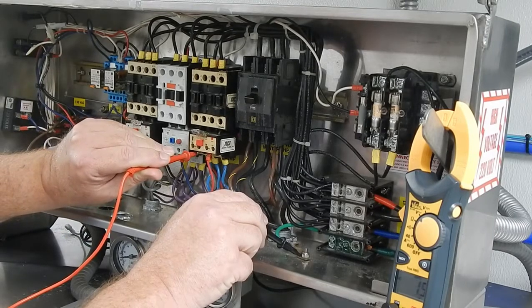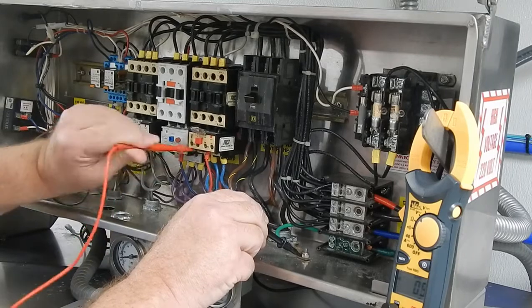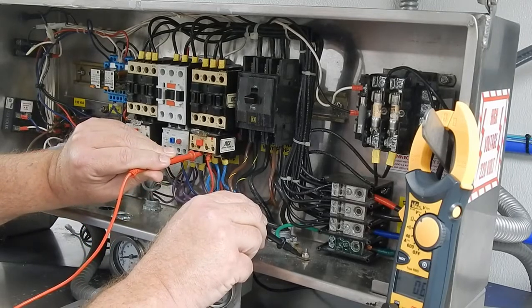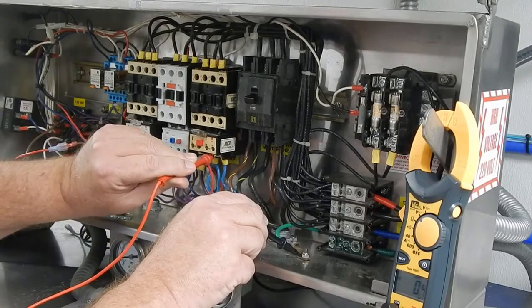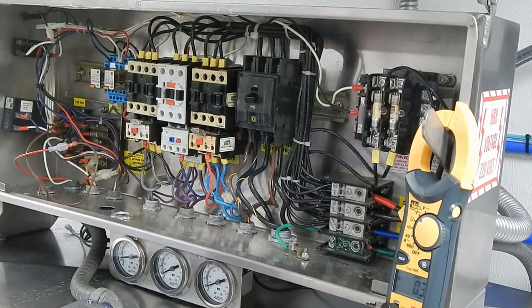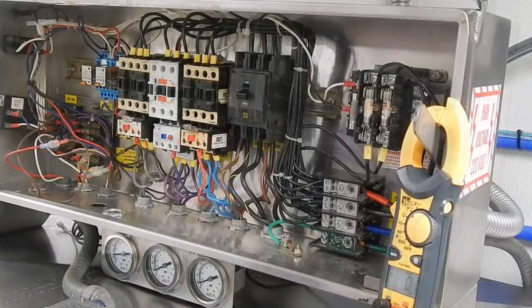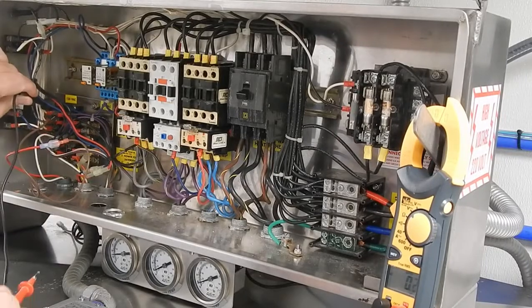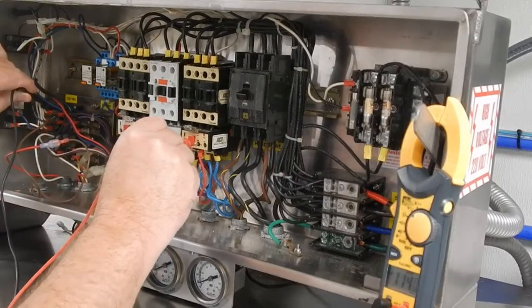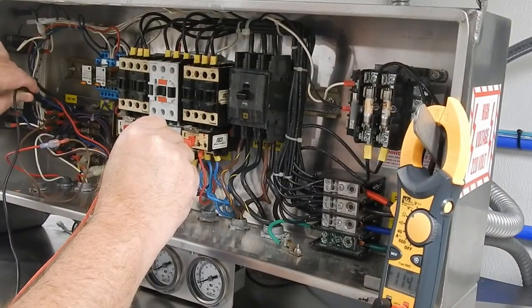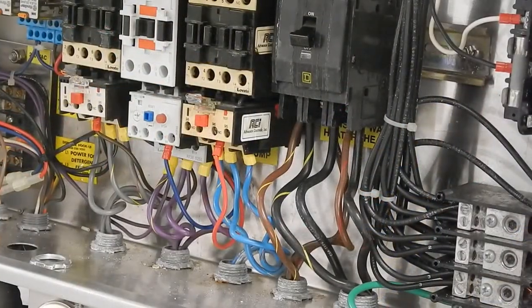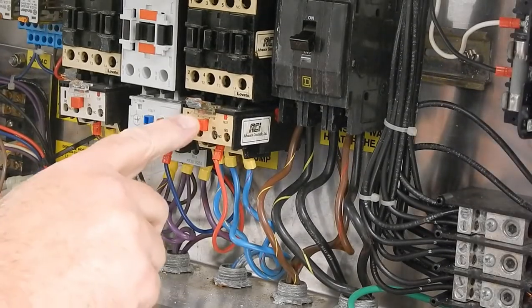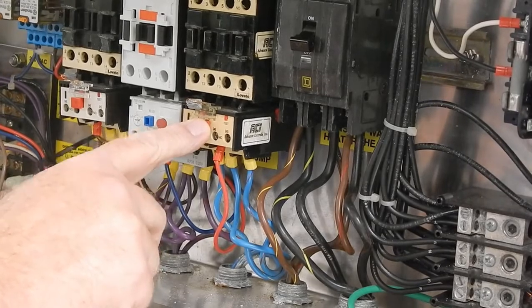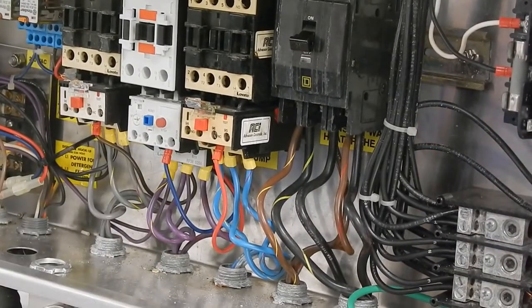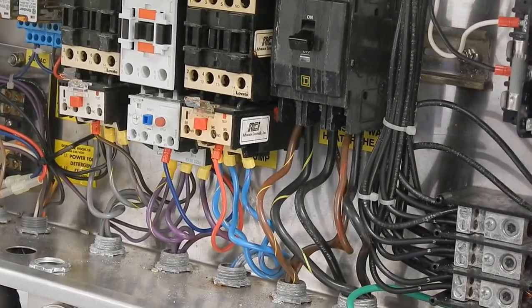Next, we're going to check to see, do we have current flowing through the contactor? If you notice on the meter, we have no current coming through. Our next check is going to be to the low voltage coming in to activate the contactor. Here, one meter lead goes on the common and the other to your power lead coming into the contactor. We do have voltage coming in. Next, we're going to try to reset the overload. As you can hear, the overload reset the motor and the motor started running.